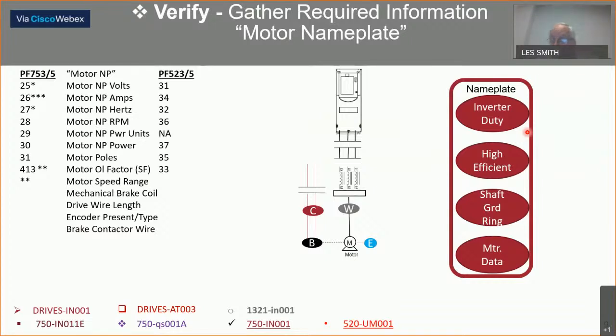Mechanical brake coil, see what's tied onto that motor. That's important to know for startup, especially to do tuning. You unlock the brake, but then to know where the wiring is for that coil. That's an inductor out there, and it could be close to some sensitive wires. Drive wire length. How far is the drive from the motor? Very important. One of the first questions, is it 5 feet or is it 300 feet? That determines a different strategy in troubleshooting.